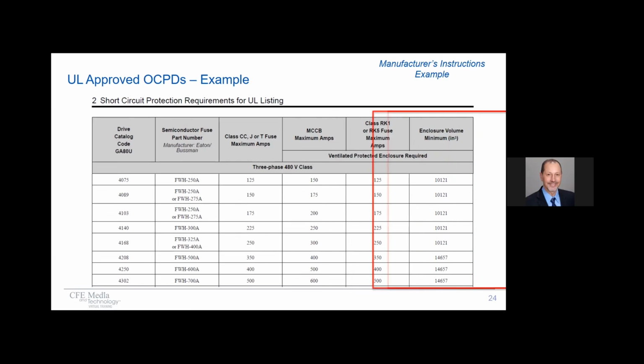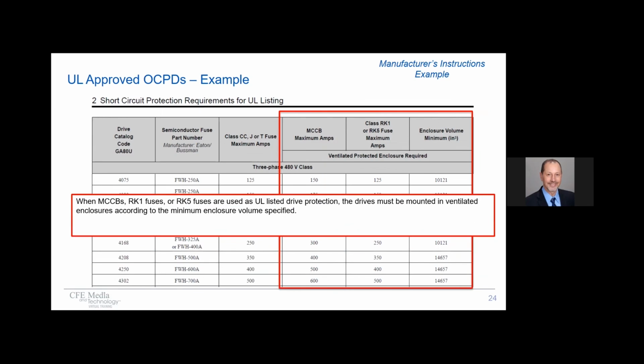But secondly, notice that some devices have limitations of use. In this case, the devices inside the red box can be used only when the drive is mounted in an enclosure. However, circuit breakers and RK fuses have the additional requirement of minimum enclosure size, and this is stated in these instructions. You must always pay attention to the fine print and may find differences between drive sizes and voltages. Again, this is just one example. You must use specific supplier instructions.